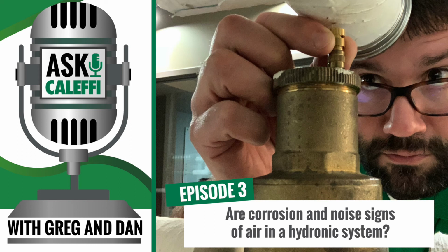With all of our air vents, they're designed to be serviceable. You can remove the cap and float and clean the pin out if you have an issue there. You can remove the vent assembly and clean that out. We have replacement vent assemblies, so you're not limited to having to replace the whole unit. We sell replacement cap and floats too, so you're not getting into a position where you have to replace the whole unit. That's what's nice about them, they are very serviceable.